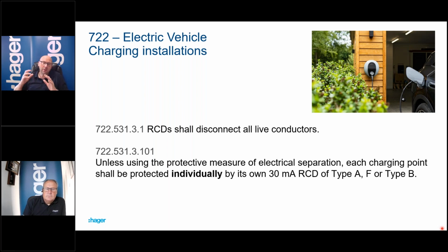So if the circuit starts to see any more than that, the RDCDD cuts the charge point off, preventing the type A RCD from being compromised. Okay, so it won't be blinded and it'll still be operational. As soon as the level of DC settles down, the charging recommences and it carries on. So the two are working together.